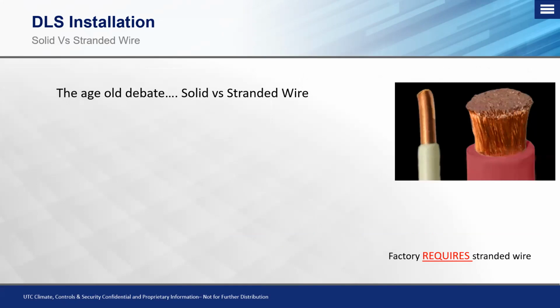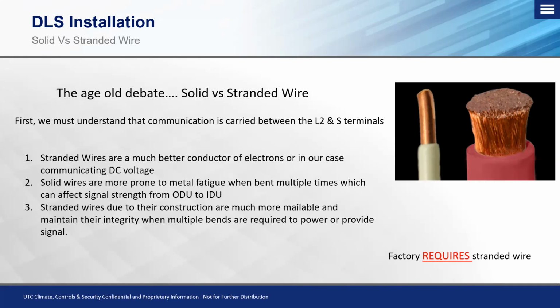Now, the biggest thing is, guys always ask me, well, I've used solid wires on these ductless systems before and never had any issues. How come Carrier is saying that we can't use solid wire, we have to use stranded? Well, let's get into it and understand the basics. So first, we must understand that communication is carried between the L2 and the S terminals. And on the 115 volt systems, we know it's carried between the N and the S terminals. So we know stranded wires are a much better conductor of electrons, or in the case that we're dealing with, in communicating DC voltage from our outdoor unit to our indoor unit.